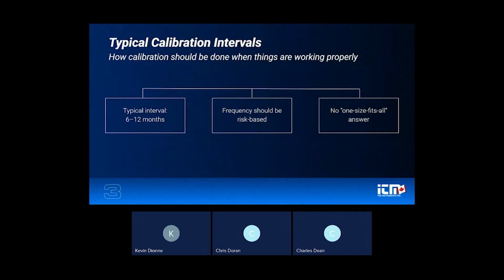So, how calibration should be done when things are working properly. When it comes to calibration frequency, the most common interval you'll hear is somewhere between 6 and 12 months. This is often stated by manufacturers. When you buy a tool, they'll tell you, hey, this comes with a calibration certificate and it needs to be recalibrated every 6 to 12 months.